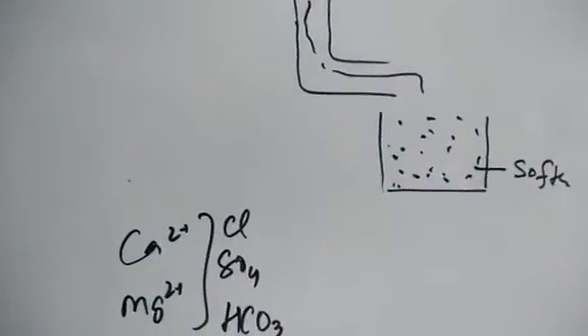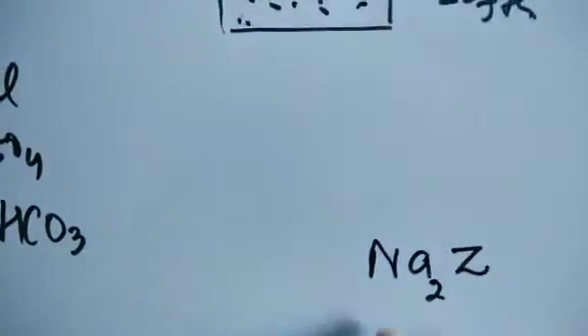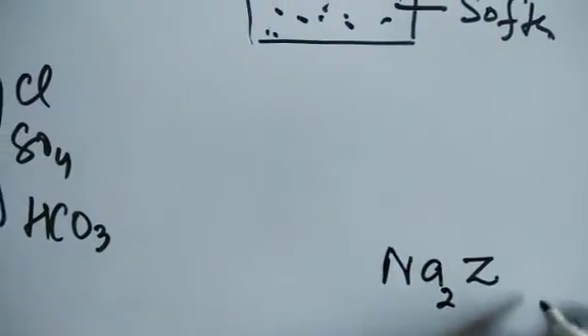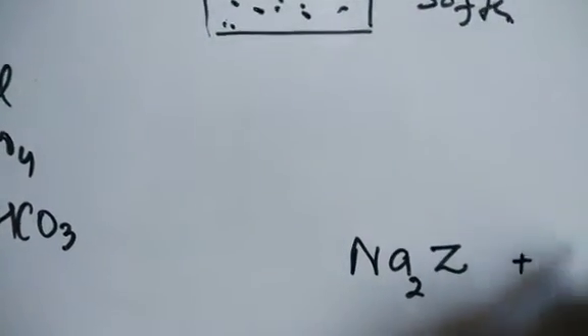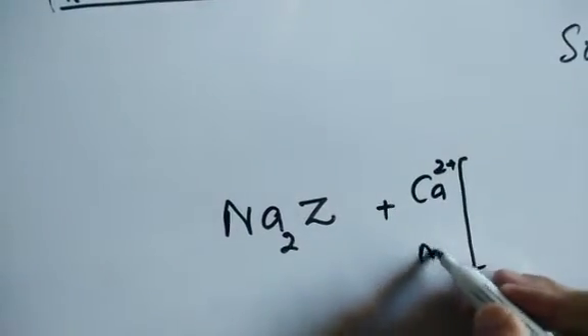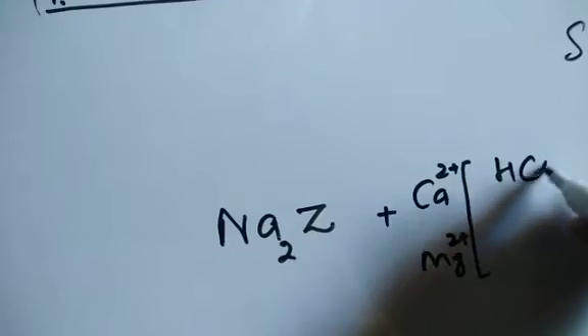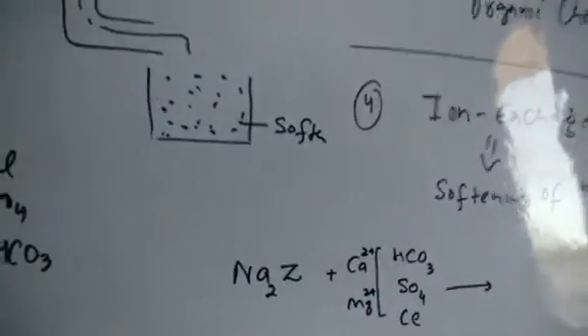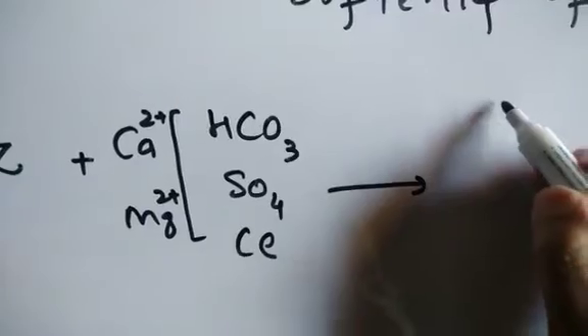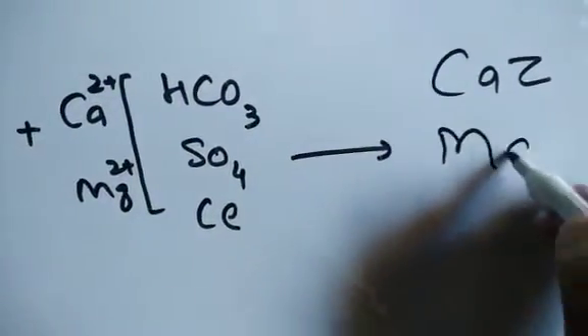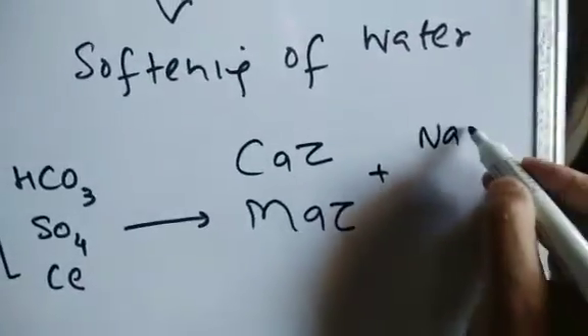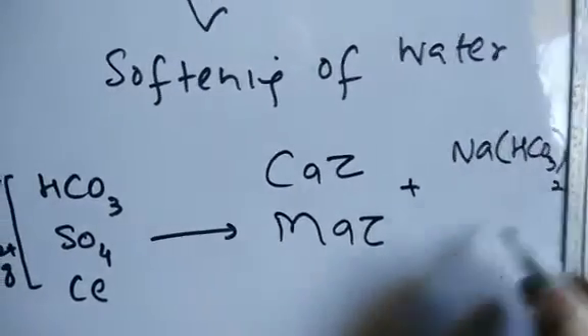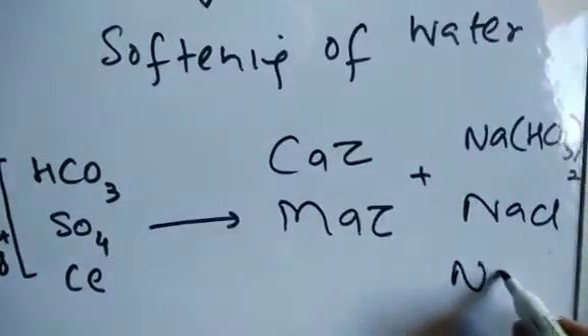We can express this as a reaction: sodium zeolite (Na₂Z, sodium aluminium silicate) is treated with hard water containing calcium and magnesium salts. The calcium and magnesium ions occupy the zeolite sites, producing calcium zeolite, magnesium zeolite, plus sodium bicarbonate, sodium chloride, and sodium sulfate in the effluent water.